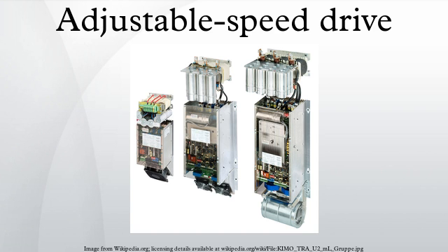In general, a VFD in its most basic configuration controls the speed of an induction or synchronous motor by adjusting the frequency of the power supplied to the motor. When changing VFD frequency in standard low-performance variable torque applications using volt per Hertz control, the AC motor's voltage-to-frequency ratio can be maintained constant, and its power can be varied between the minimum and maximum operating frequencies up to a base frequency. Constant voltage operation above base frequency, and therefore with reduced volt per Hertz ratio, provides reduced torque and constant power capability.